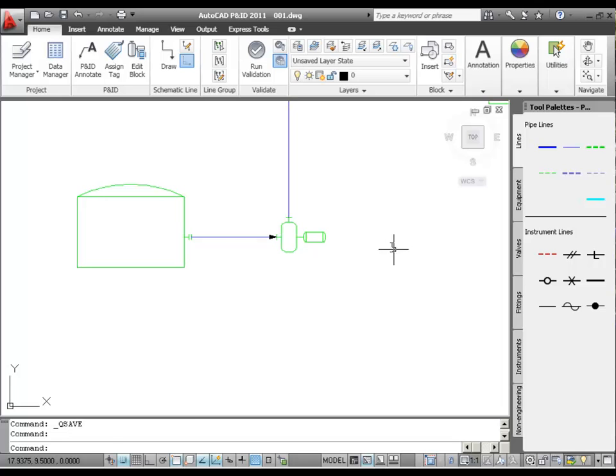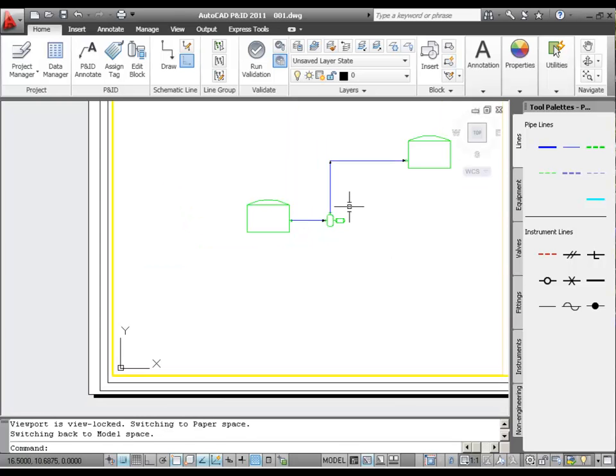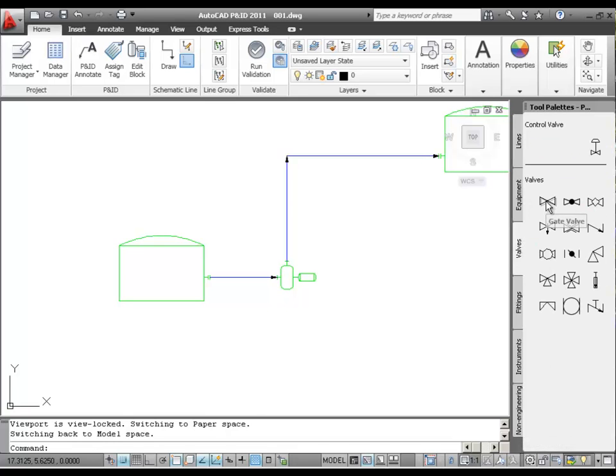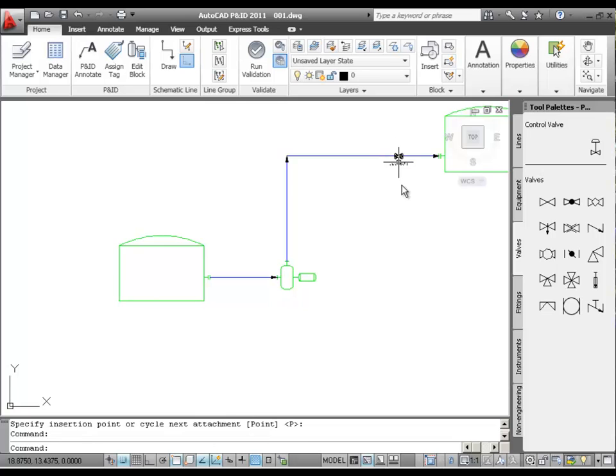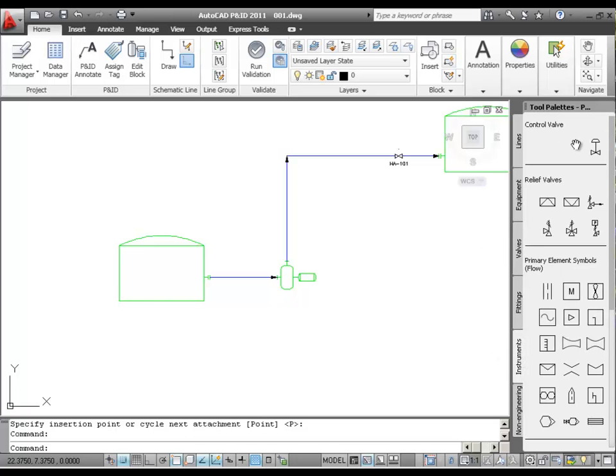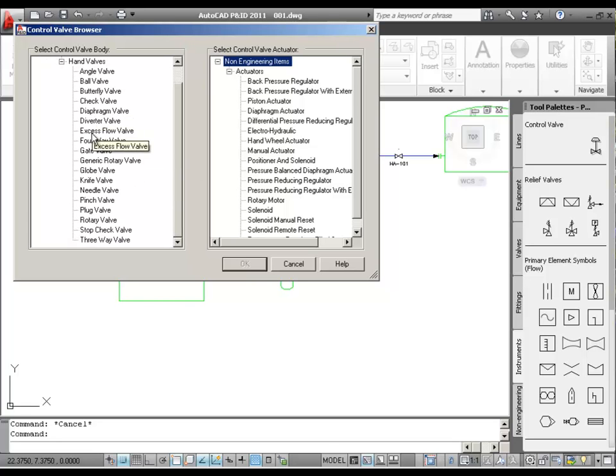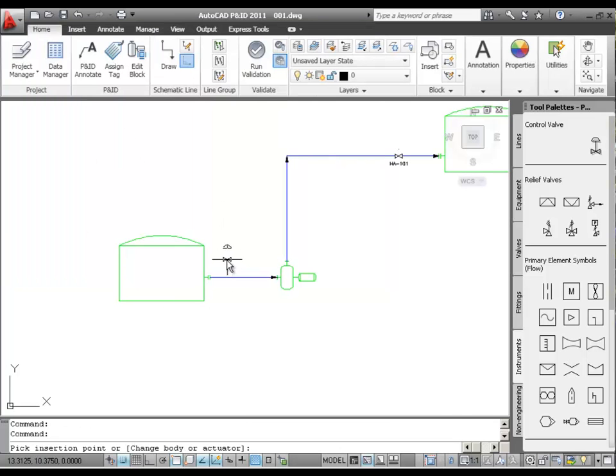Now we're going to add some inline components, starting with valves. I'm going to zoom in around the discharge line of the pump and change our tool palette to the Valves tab. First we're going to place a gate valve, so we'll click the gate valve symbol and then click the horizontal line to place the valve. Next, we'll add a control valve to our drawing, which we can get from either the Valves tab or from the Instruments tab. We'll click the control valve on the tool palette. The very first time you pick a control valve, it'll ask you to set the default body type and actuator type. I'm going to pick gate valve as a body and diaphragm actuator for my top works, and press OK.